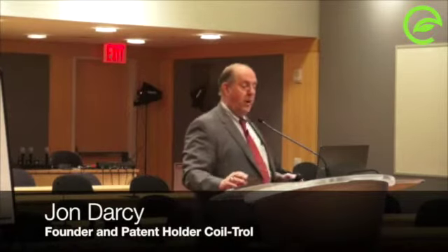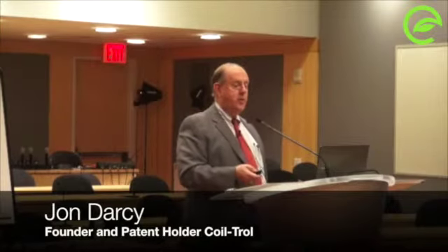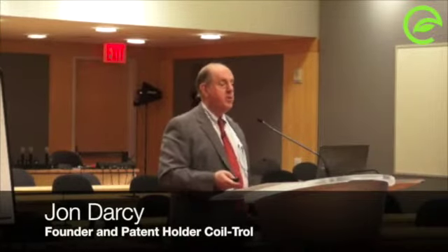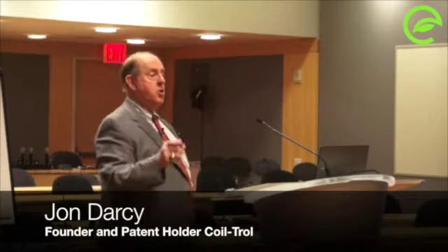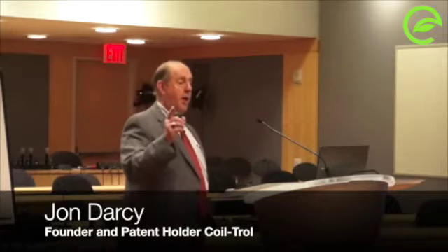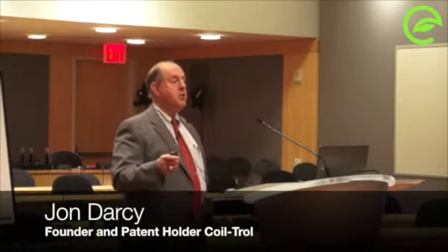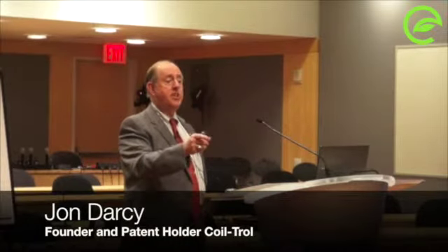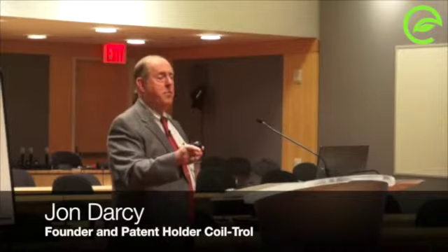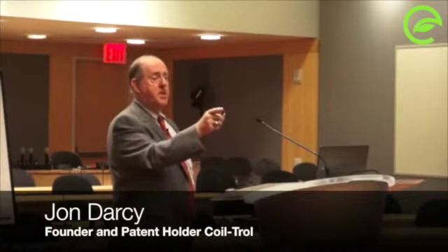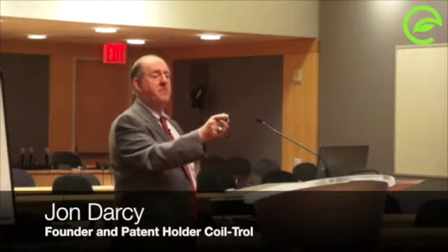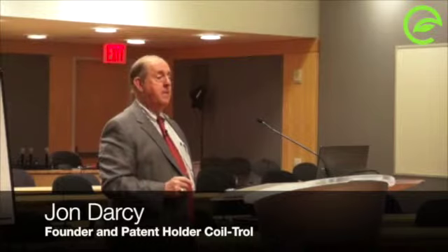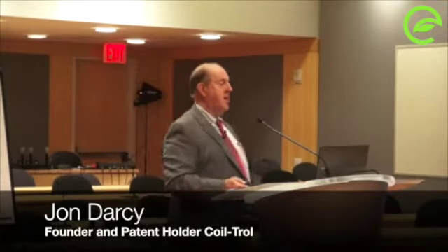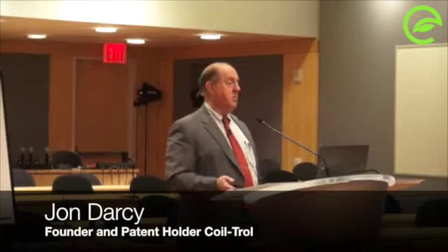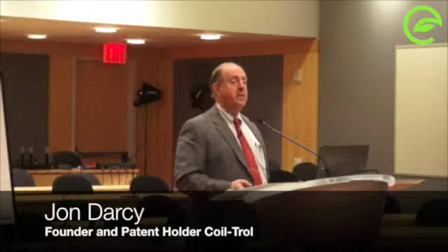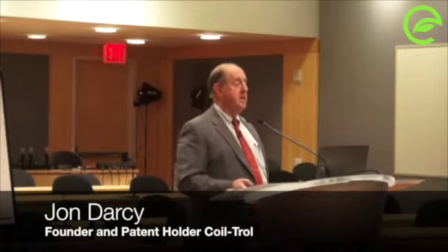So what we are trying to do is we use the grains of moisture. The problem with changing the discharge air temperature is losing the humidity control. So we use what I call grains control in the Coil-Trol. I measure the temperature and humidity, and I calculate the grains. I know if the grains are 64 or 65 grains per pound of dry air, and my temperature is between 72 and 75, my relative humidity is someplace between 50 and 55, which means my people are comfortable, okay? And I have no interaction between the two control systems. In other words, my two control variables, because the absolute humidity is totally independent of temperature.